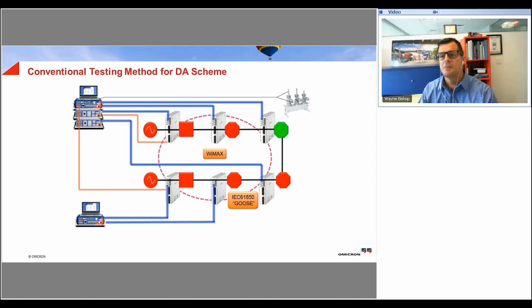So let's talk briefly about the conventional method of testing these DA schemes. Typically, these are only done in the lab, and for a lab test of a DA scheme, all devices are set up in a lab environment. These tests are typically performed as a proof of concept for a new project or acceptance testing of a scheme prior to installation in the field. This is usually done using secondary injection test devices connected to each recloser control, with various pre-programmed test sequences that can be executed to test the logic and communication, which are essential to the scheme.